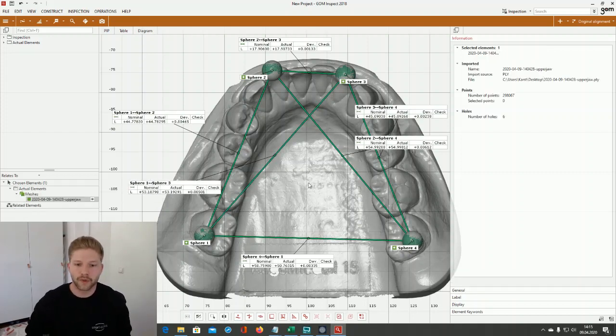Of course, we are performing these tests not just once for the device. You have to do it directly after the calibration and after 100 scans or 1,000 scans to also check the precision. And that's basically how we work in the R&D department, and just a little insight on how to check the accuracy of scan data. Don't always have a look at the beautiful 3D files you see in the viewer. Always make sure that you have the possibility to also check it.